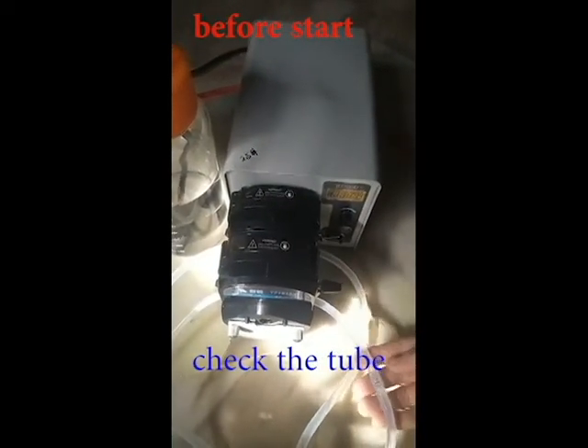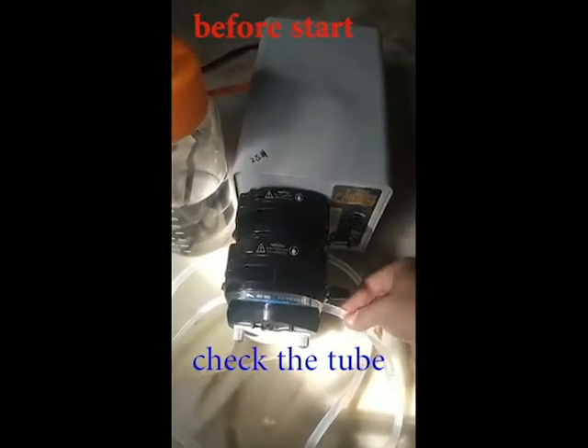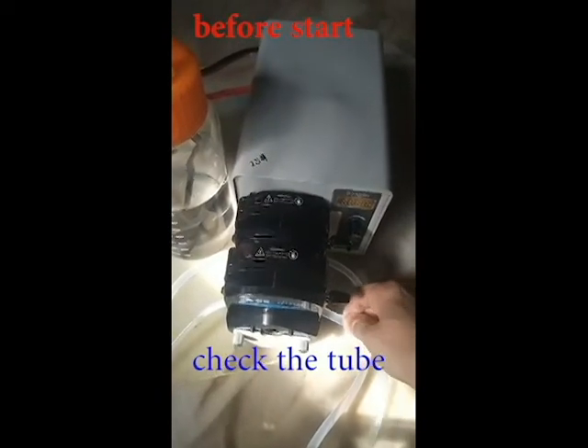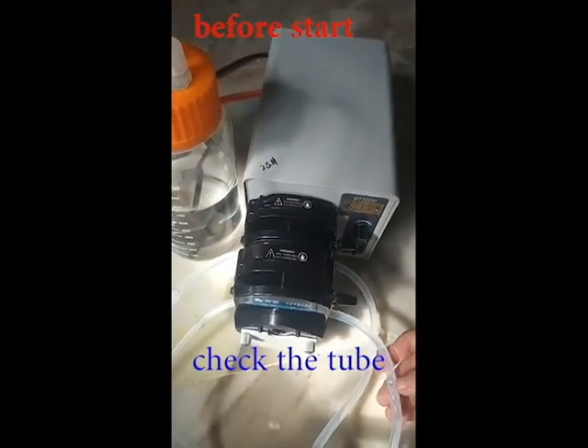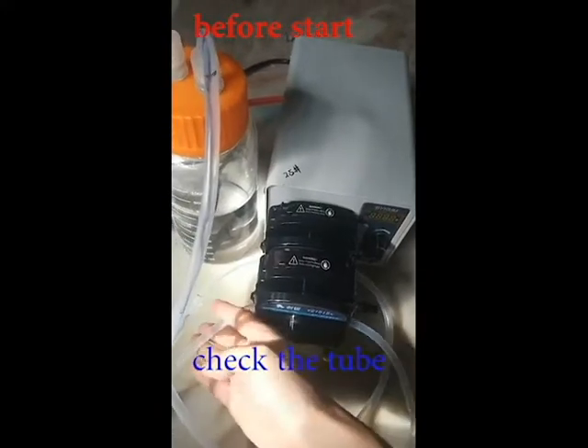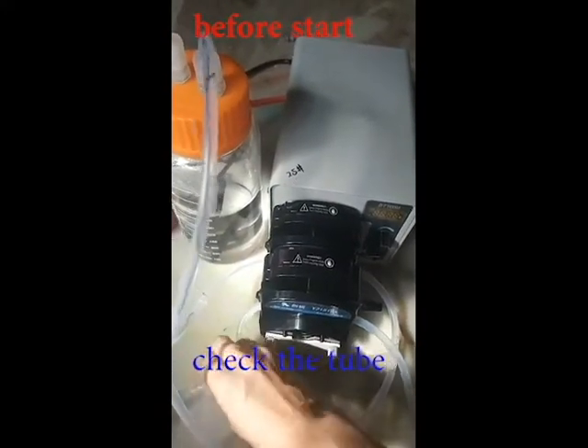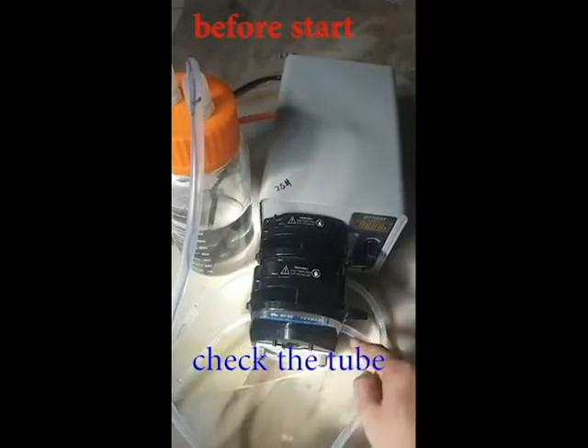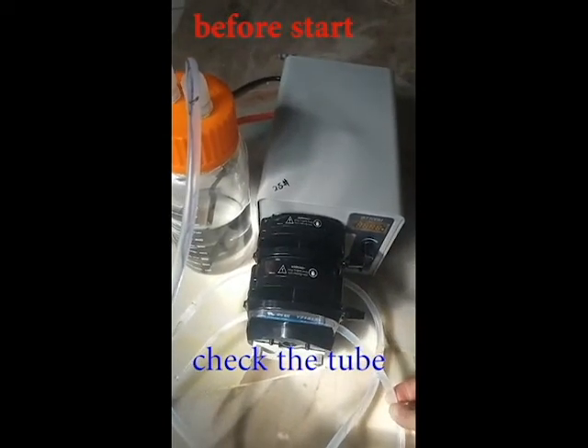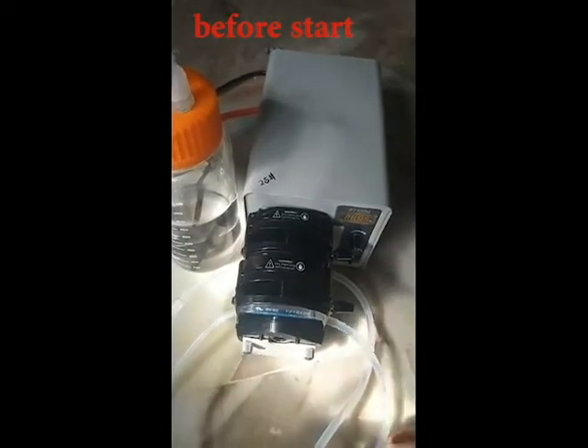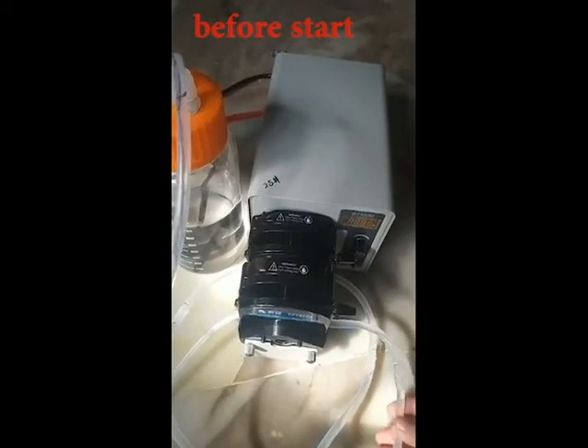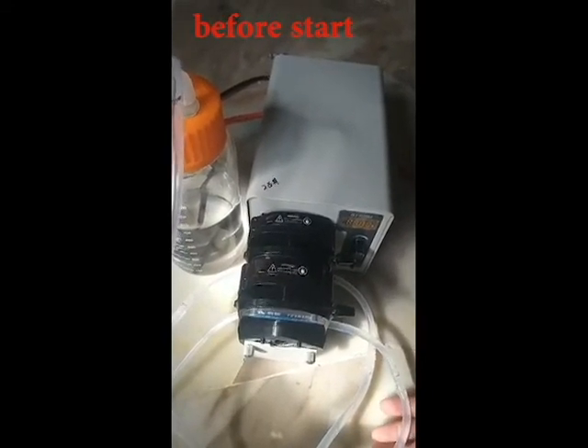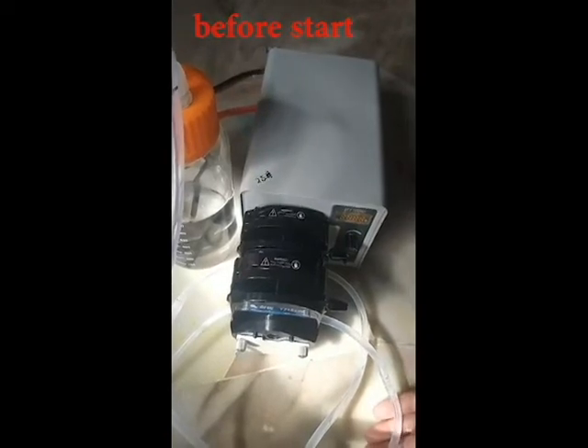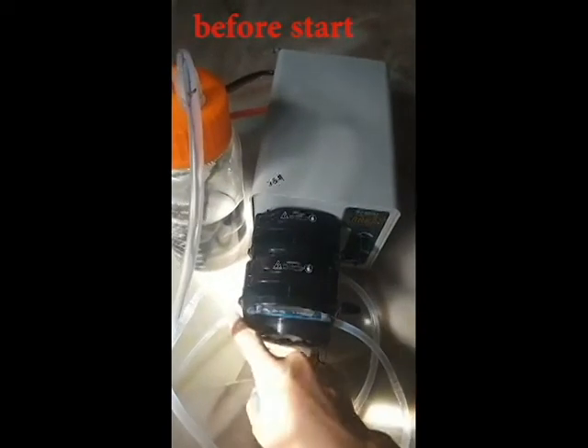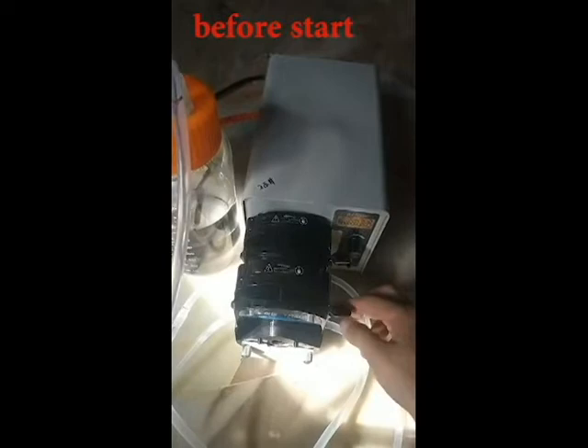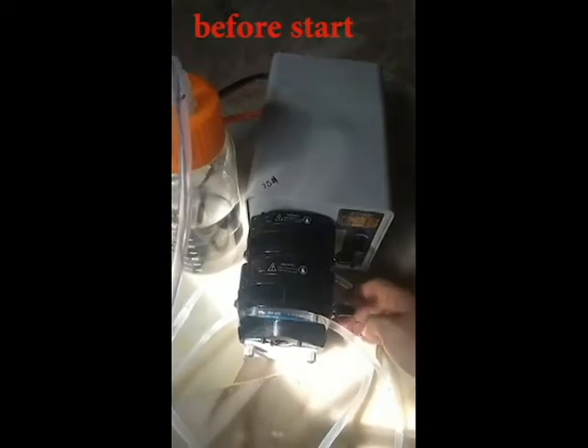And when your tube has been in use for a longer time, you need to check the quality of the tube. The most important part is from here to here. You can see we installed an adapter here. This is to make it easy to change the tube, because the outside tube is not a problem. It's only liquid passing through, so the life will be much longer. But the internal part here, since it's always rotating, its life will be affected.